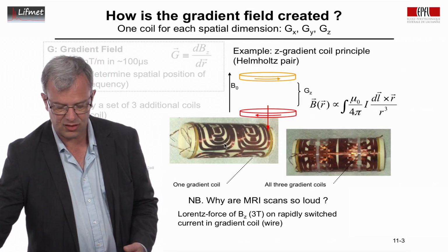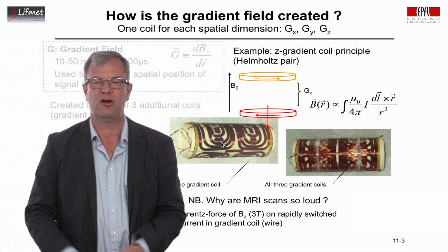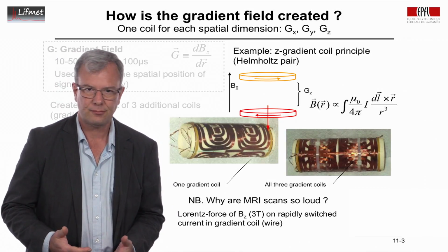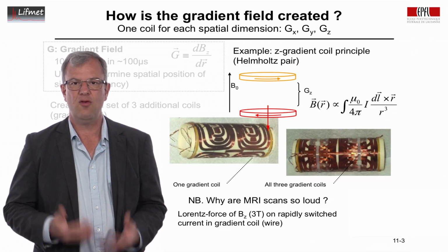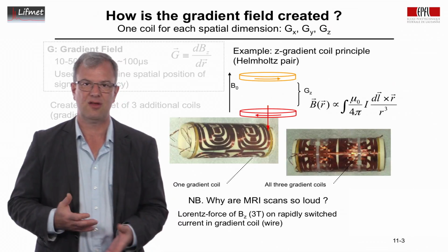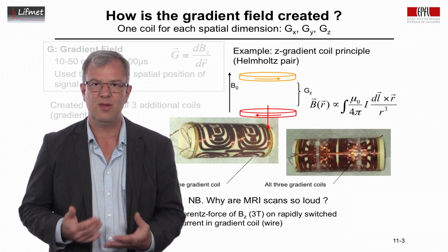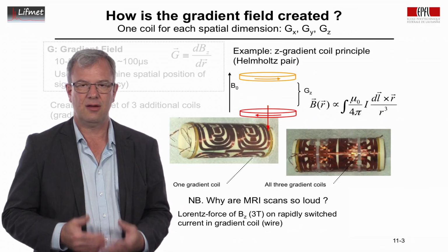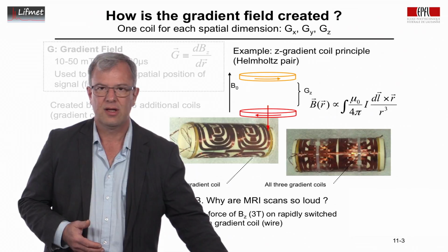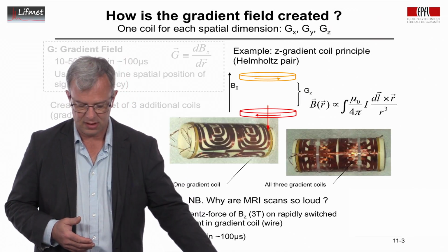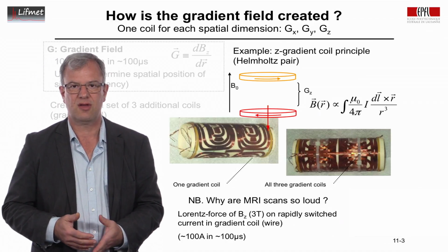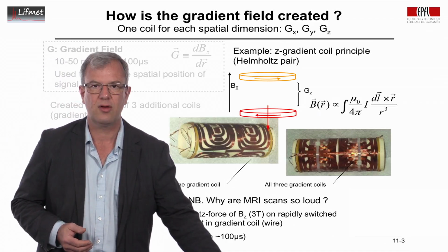Here it's the copper structure that hammers on its support. The support doesn't move, like if you hammer on a table, like this table here. The support cannot move, but you still have this knocking sound, and that produces very strong forces. The examples with the Coke can are just mere illustrations of the kinds of forces that are in there. To give you an idea what we're talking about, one switch is typically 100 amperes in about 100 microseconds. That's the kind of forces that we're looking at.